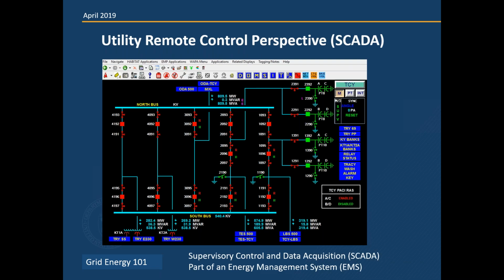So almost every utility has a SCADA. It stands for Supervisory Control and Data Acquisition. It's part of an energy management system, and what a SCADA system does is allow the system operators to operate the equipment remotely. This is a completely different station. This is not the one we looked at in the two previous slides. Here the common thing you want to see is the red squares. Those are circuit breakers. The system operator can click on that and open that breaker and de-energize the line. And this happens to be 500 kV. Next slide, please.